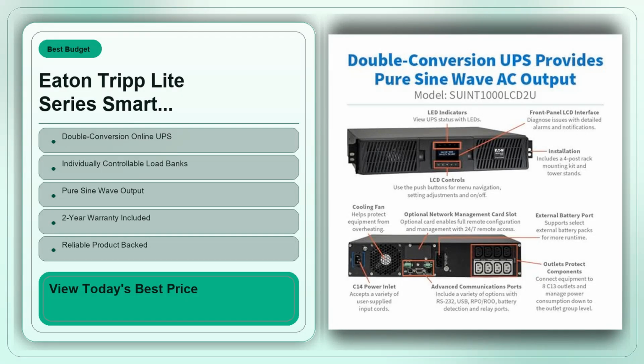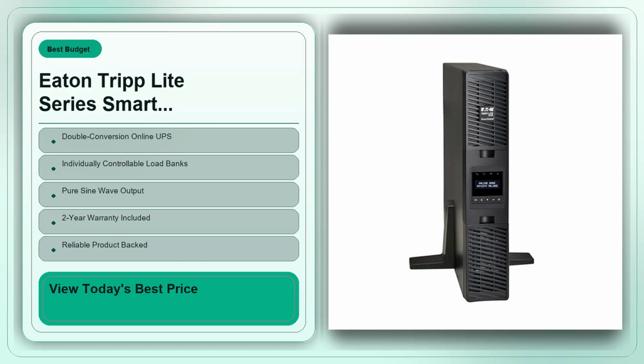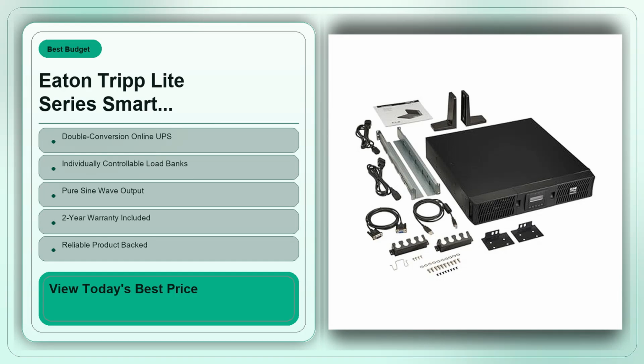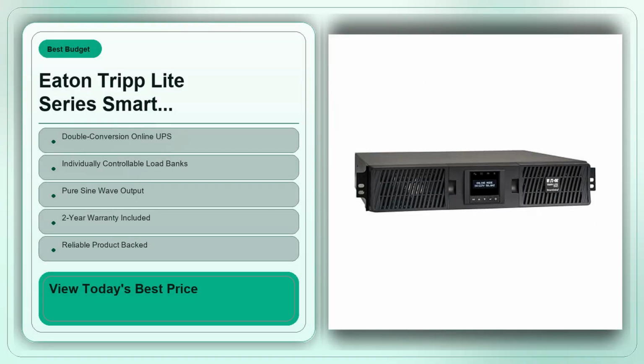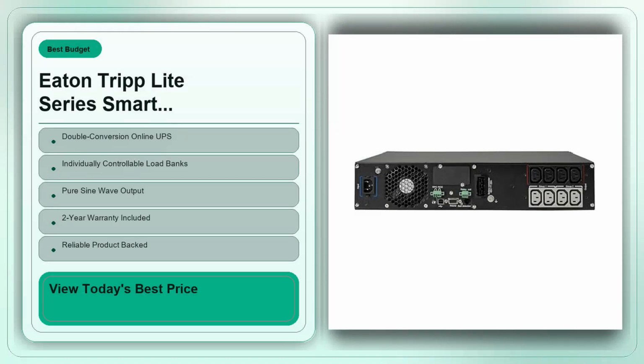The 1000 VA, 900W rating will cover a single workstation with a decent graphics card, but you'll quickly see the runtime drop to under 5 minutes under full load. For a typical office environment with a handful of workstations, a line interactive UPS, or even a quality surge strip, would be more cost-effective. Let's talk about the practical strengths that show up when you actually install this thing.